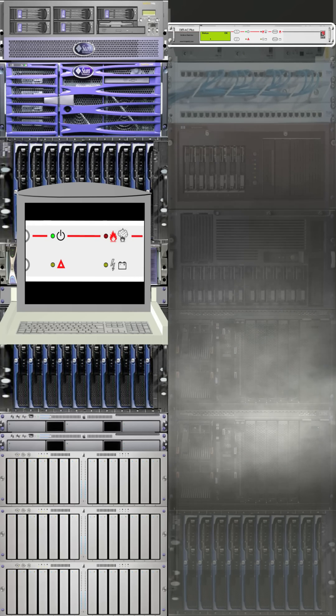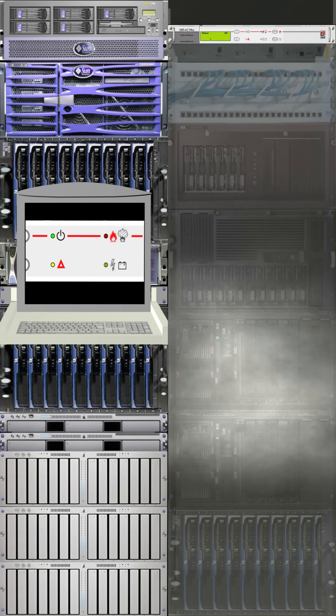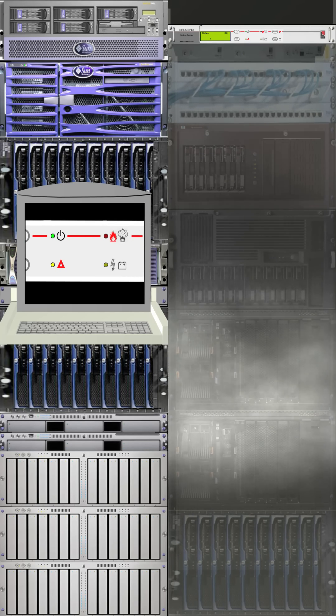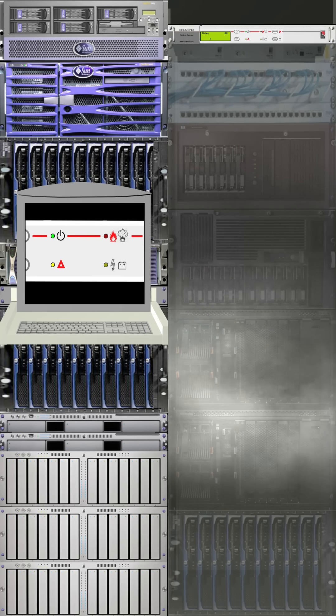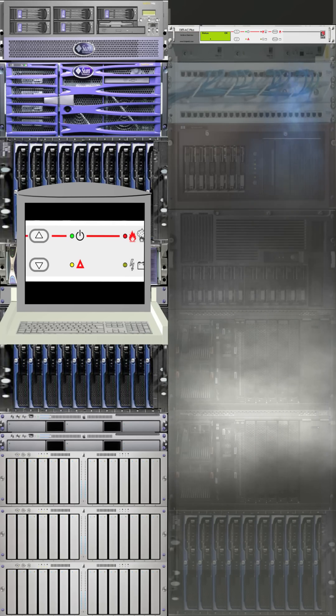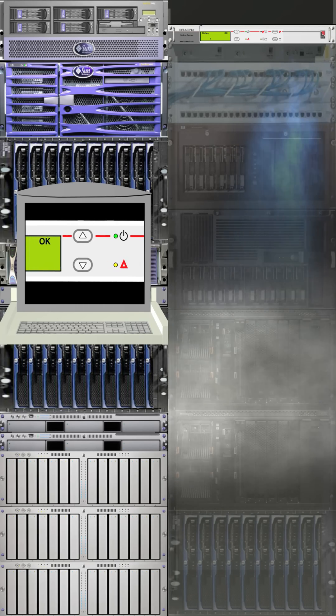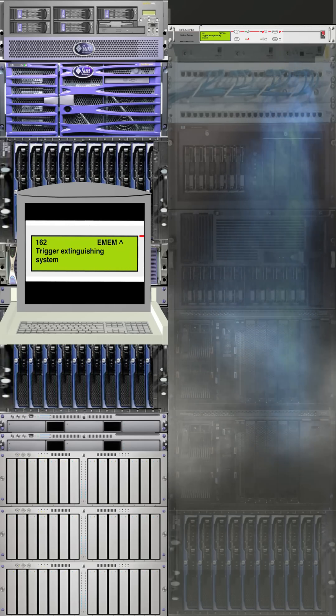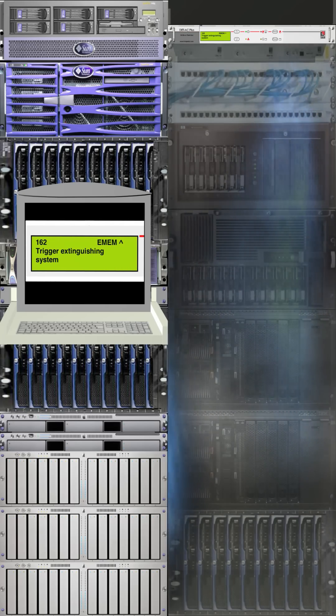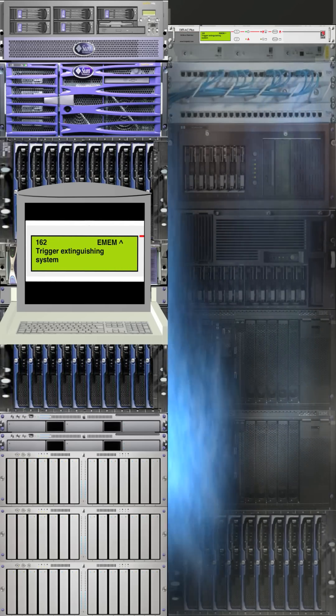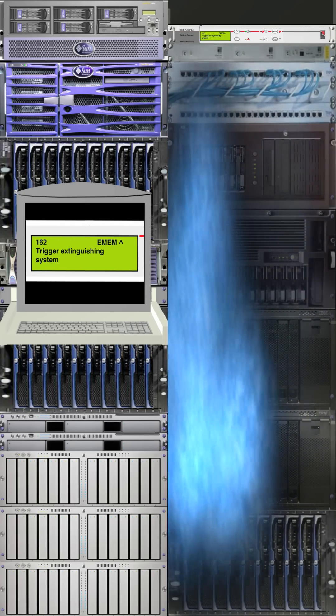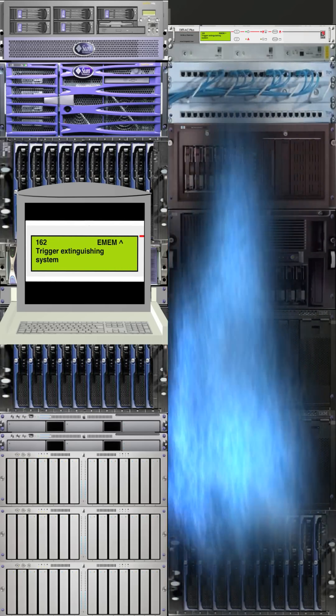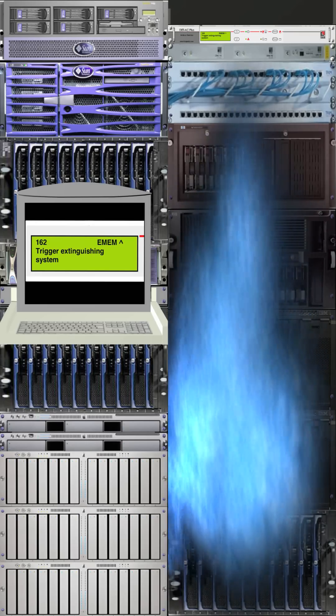If the first smoke alarm detects smoke particles, a pre-alarm is triggered. If the second alarm likewise detects smoke, then the extinguisher system is activated and the Novec 1230 gas is released into the rack, therefore preventing a risk of a major fire from developing.